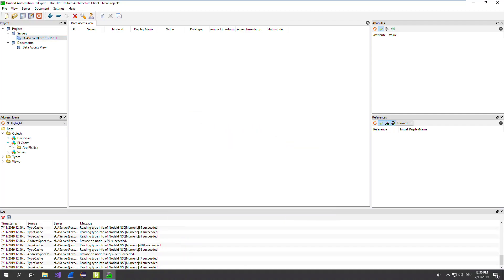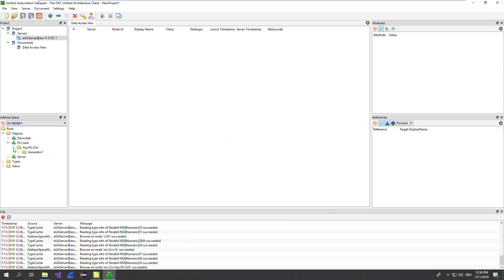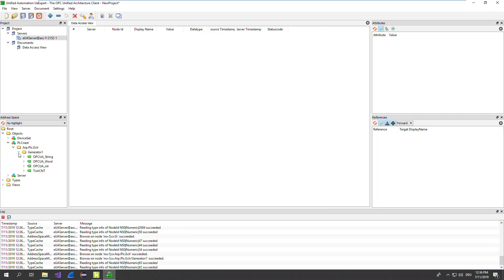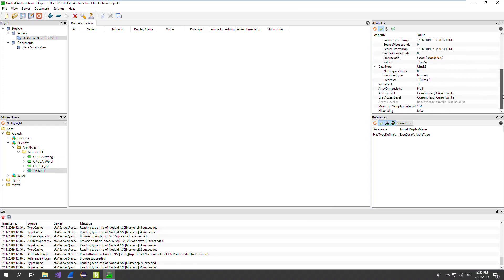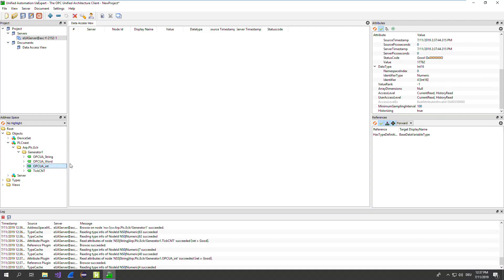So here you can see the variables we have. And let's start with this one. This is a normal variable. When you go to the status, you see historizing is false. Now go to one of the three we added to the data logger in the previous tutorial video. Click on that. You see, historizing is true. This means you can call the history of this variable, which is stored in the data logger of the PLC.